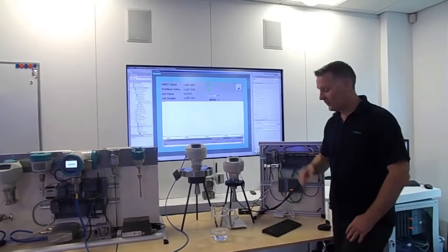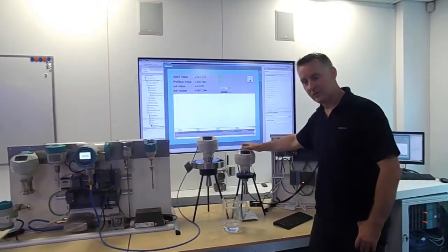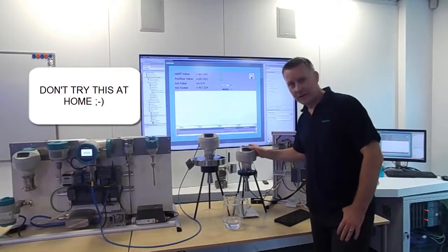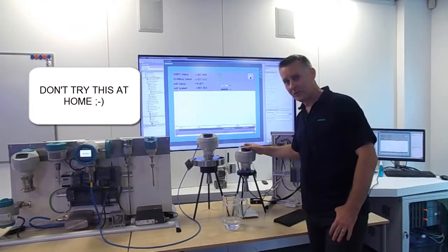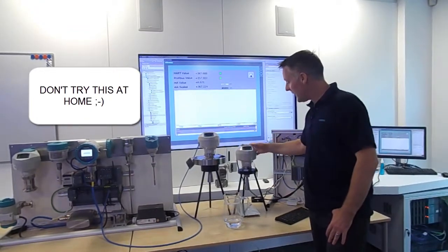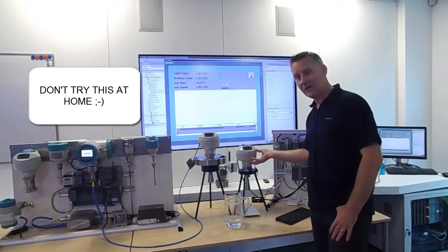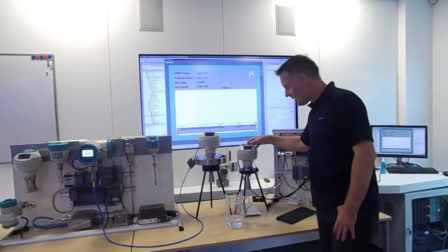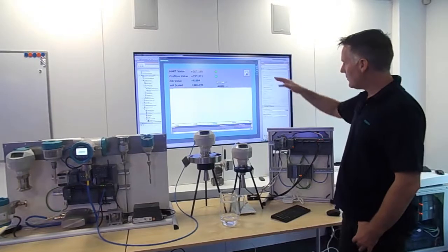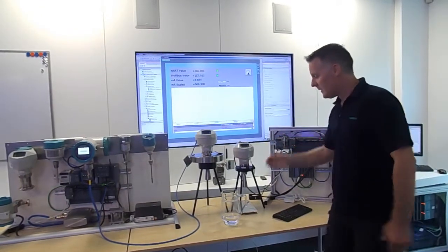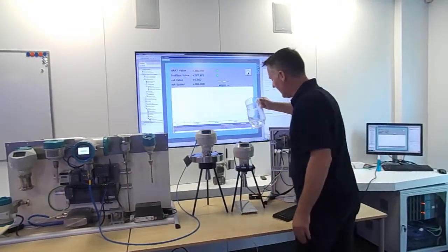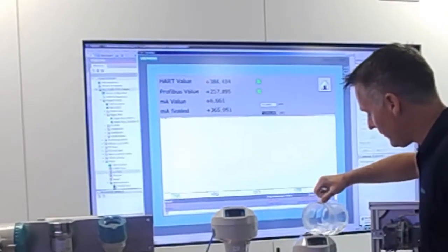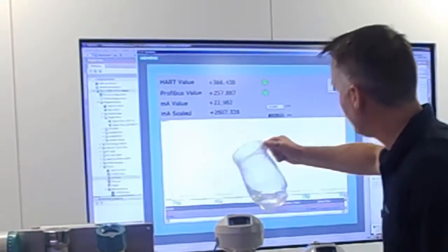Okay, so the next stage is to put some water inside of these junction boxes. I would say that we are trained professionals and you shouldn't be tipping water into any instrument. The LR5250 is made and encapsulated inside so the water is not going to get into the electronics. It's purely just going to get to the terminals and the cables. So I'm logging this data and as you can see the process values are pretty steady. It's pretty extreme. I'm going to do a bit of accelerated aging here. So we are going to put some into the Profibus terminal box and into the 4-20.